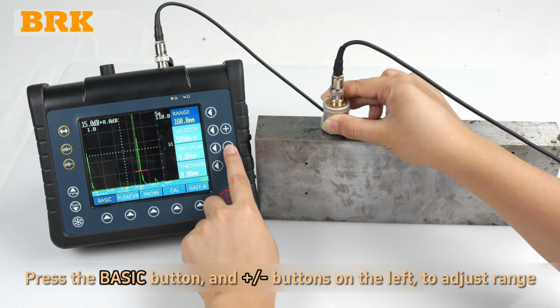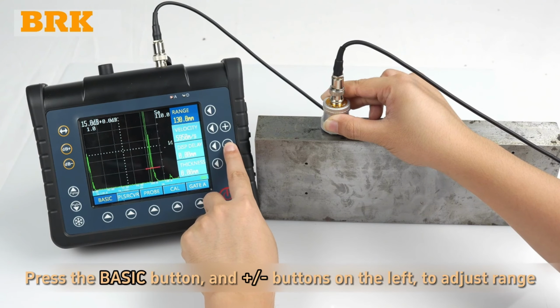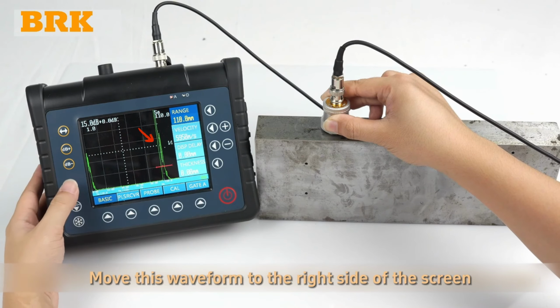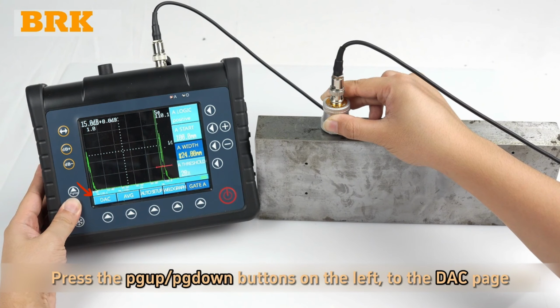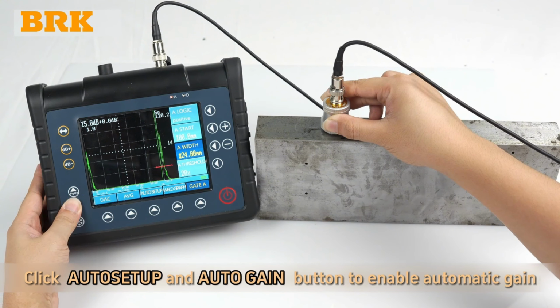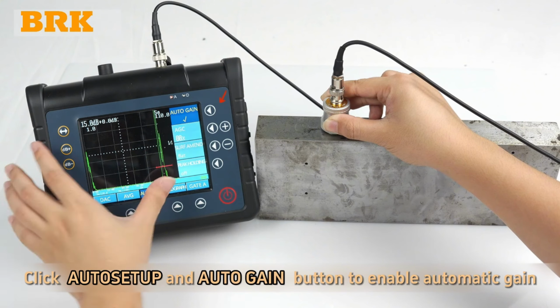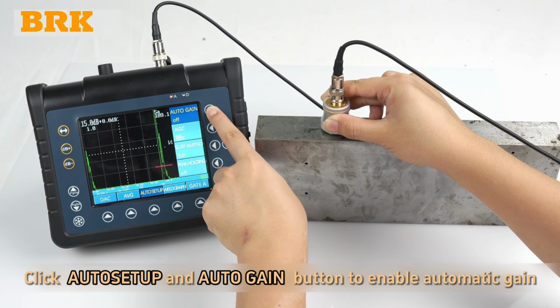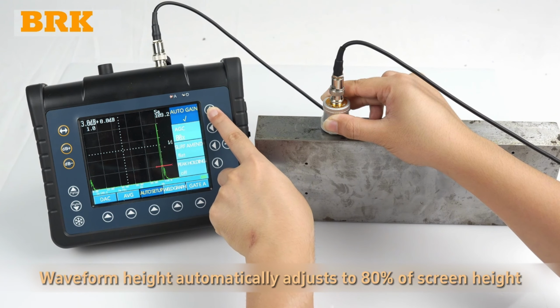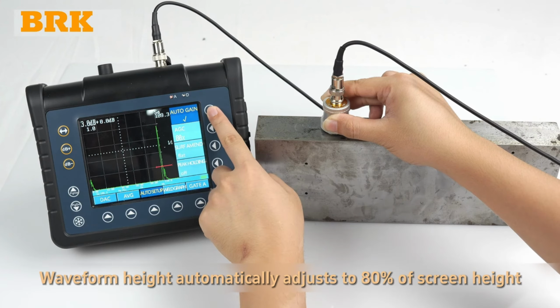Press the basic button and the plus or minus buttons on the left to adjust the range. Move this waveform to the right side of the screen. Press the page up or page down buttons on the left to the DAC page. Click Auto Setup and the Auto Gain button to enable automatic gain. Waveform height automatically adjusts to 80% of screen height.